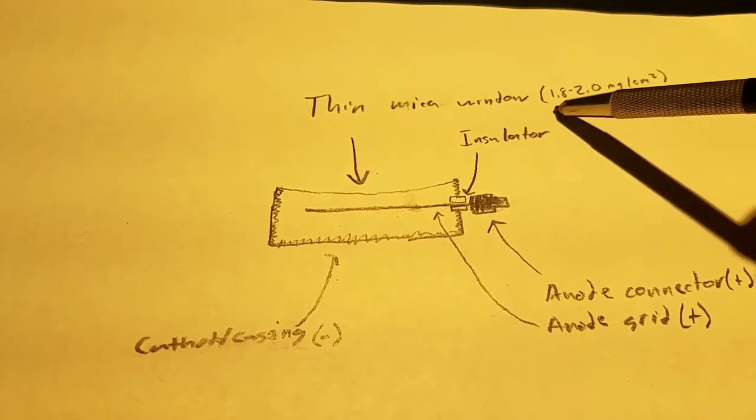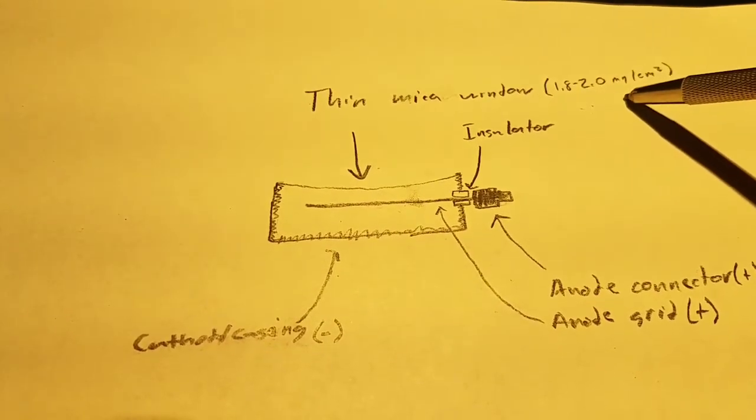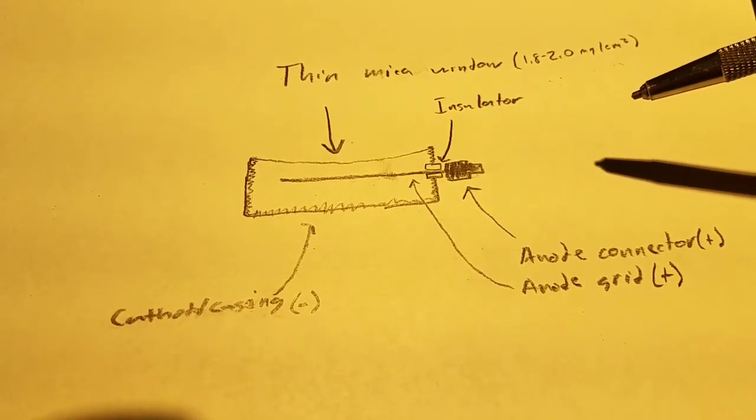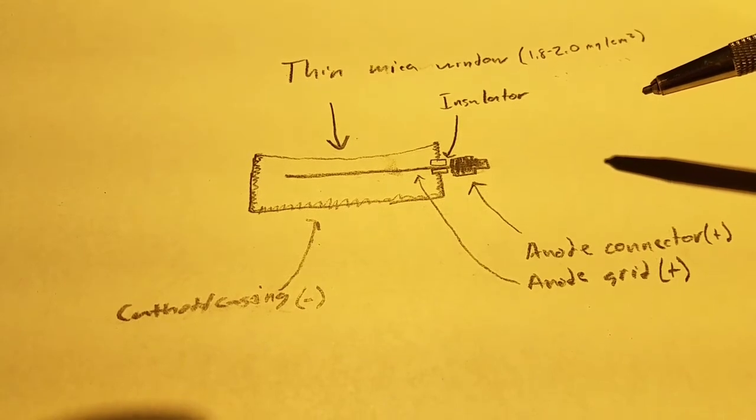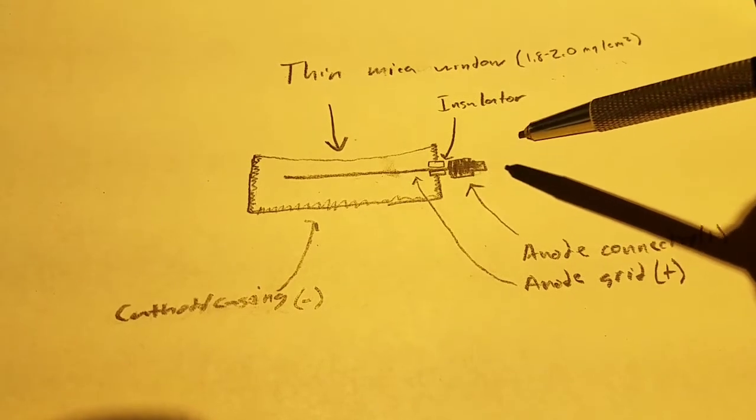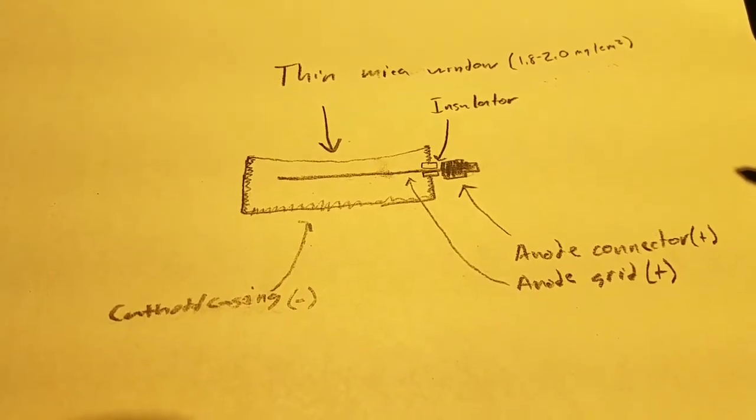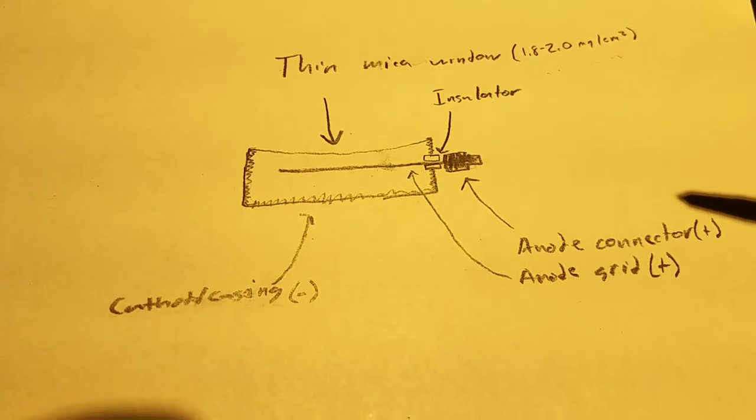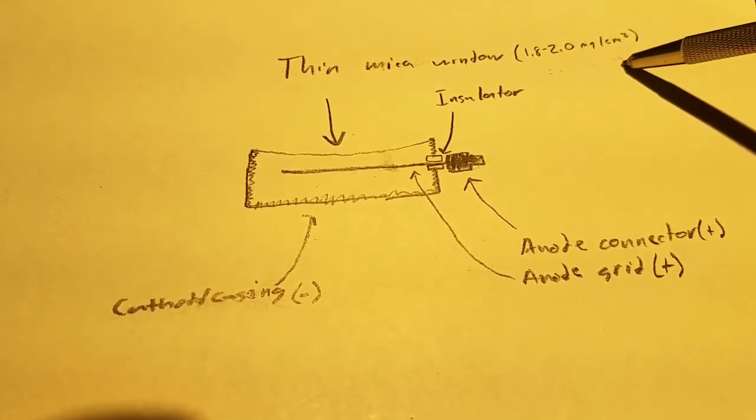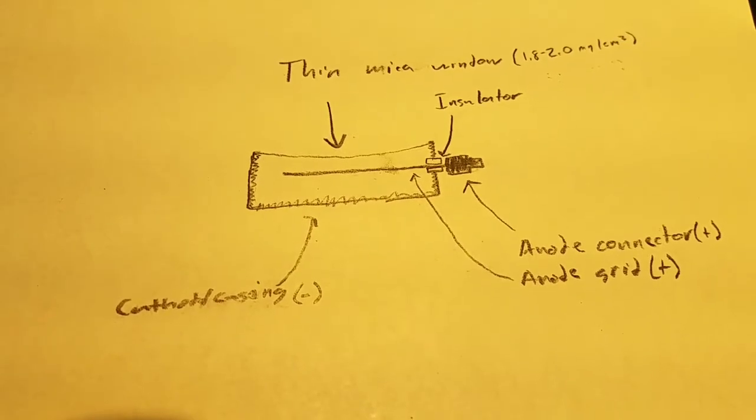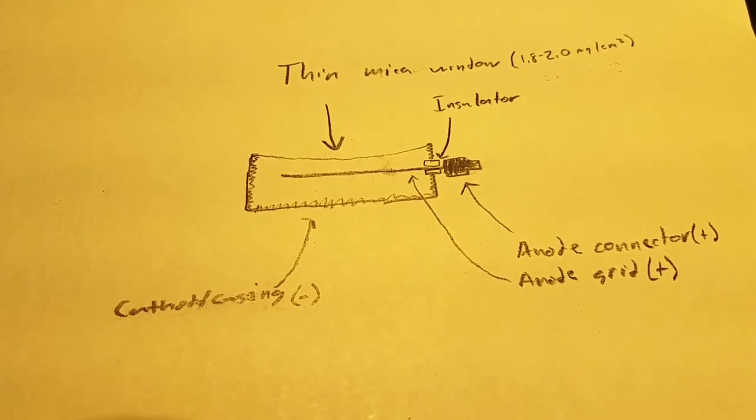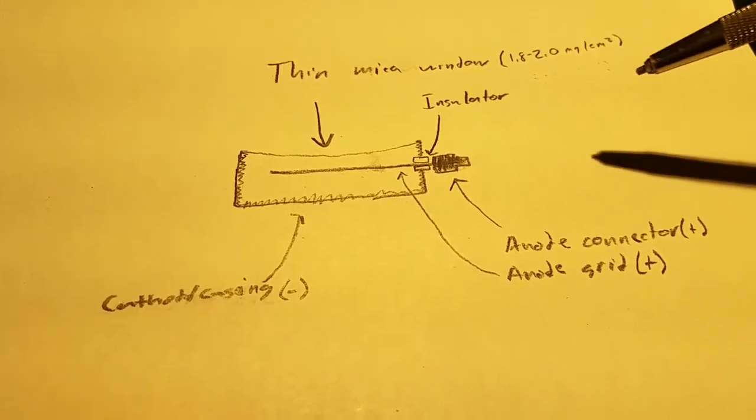To give you a sense of its density, it's 1.8 to 2.0 milligrams per square centimeter. That's mostly important because it determines what kind of particles are allowed through and at what energy levels and what percentages. This tube happens to be good for detecting alpha, beta, and gamma particles. At 1.8 to 2 milligrams per square centimeter, it can detect alpha particles starting at 2.5 MeV, which is actually decently energetic.